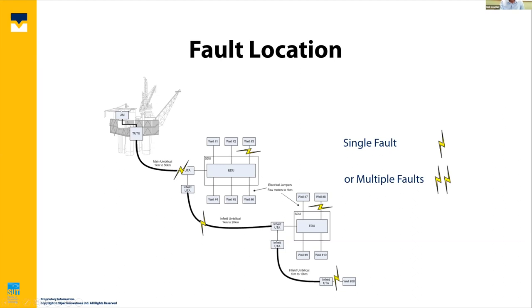The issue is, okay, your line insulation monitor is topsides. It is connected to the main umbilical. This is a made up system, but you may have multiple faults. It may not just be a single fault. If you want to repair your system, you need to find out where your fault is, and your topside line insulation monitor will only indicate that you've got a fault somewhere. To diagnose where the fault is, it's a marine intervention. On a system like this, it probably means a lot of disconnects and then reconnects subsea. As you're probably aware, if your subsea system has been down for a few years, you have calcareous or marine growth around the connectors. You disconnect them, and if the connector was good, by the time you put it back together again, it probably is not good.